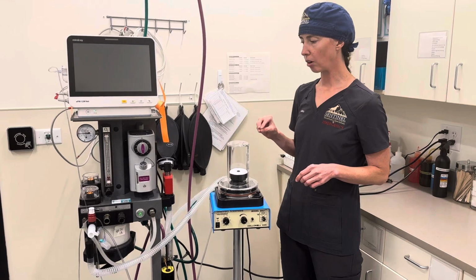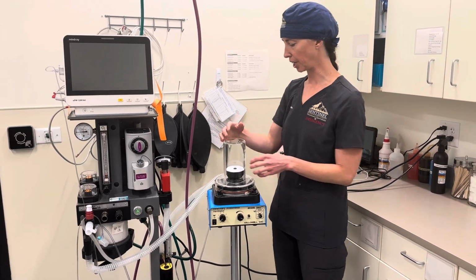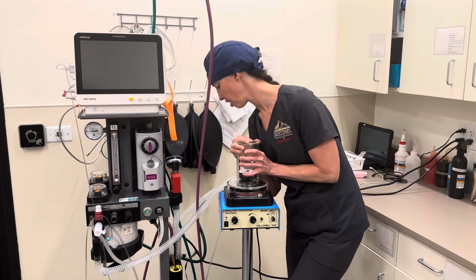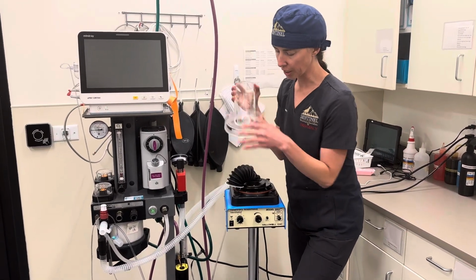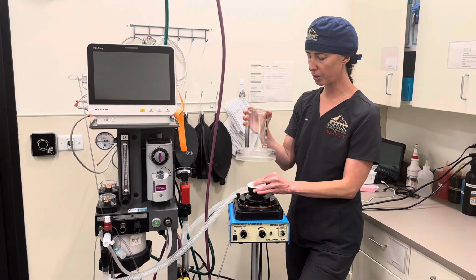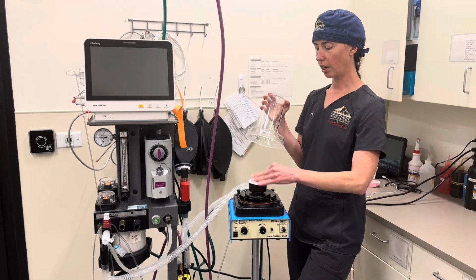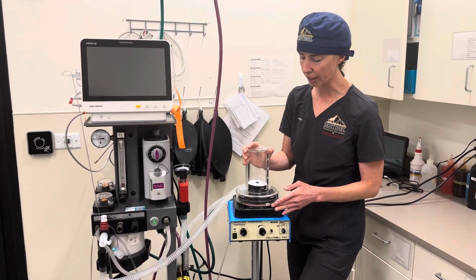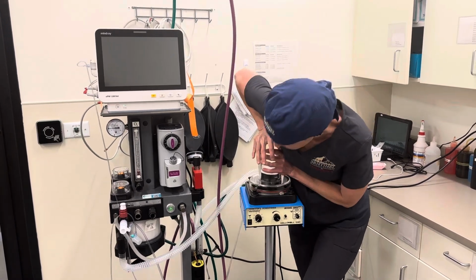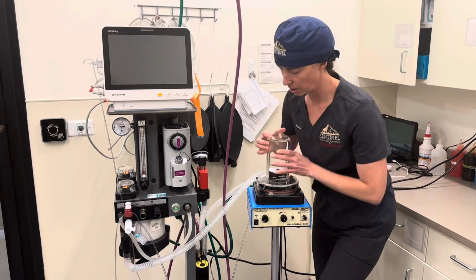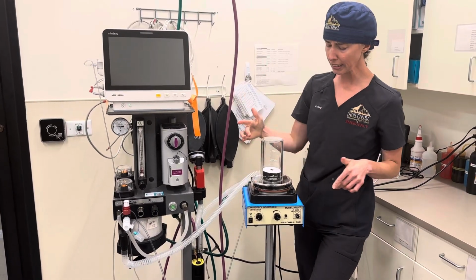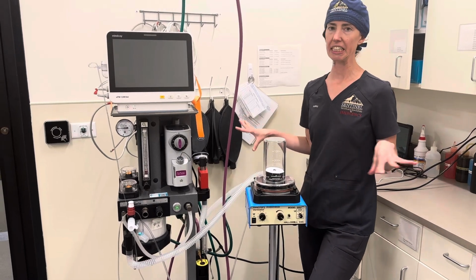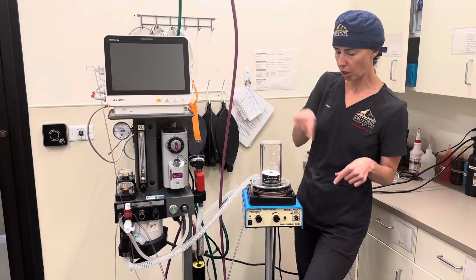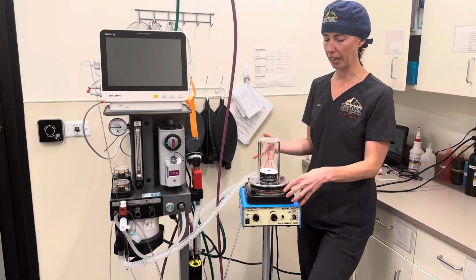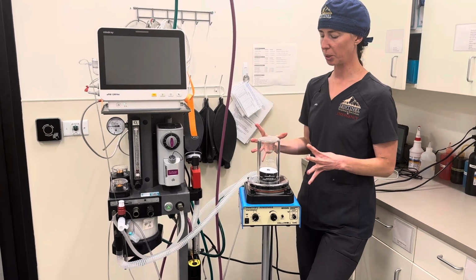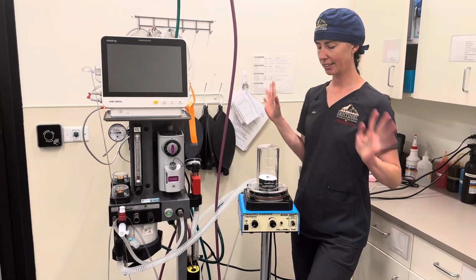So why don't we just talk about how we're going to use this in a real patient. I'm just going to put this bellows housing back on now that I took it off. These are just acrylic tubes that fit on top. This is a little bit wrinkled, but that's okay. It will level itself out once we get the machine going. You'll put the housing on, make sure you have the bellows on that you want, and then you'll twist it so you get to these little brackets. A lot of people think you need to tighten these. You don't need to tighten these brackets. There's a big rubber O-ring around the bottom of this, and that O-ring comes lubricated, so you just need to put the cylinder on and turn it into its spots, and you're good to go.